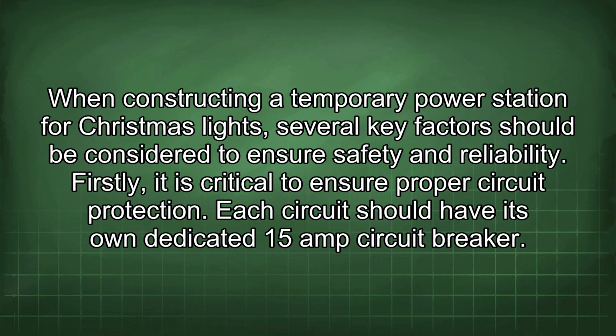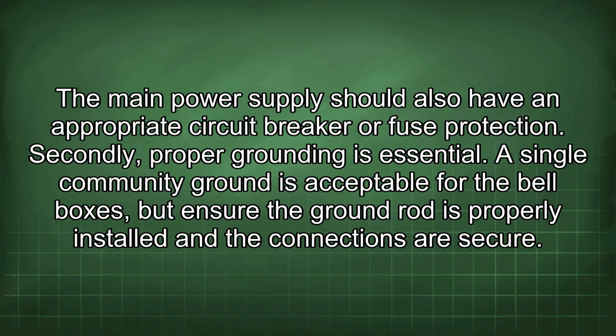When constructing a temporary power station for Christmas lights, several key factors should be considered to ensure safety and reliability. Firstly, it is critical to ensure proper circuit protection. Each circuit should have its own dedicated 15-amp circuit breaker. The main power supply should also have an appropriate circuit breaker or fuse protection.